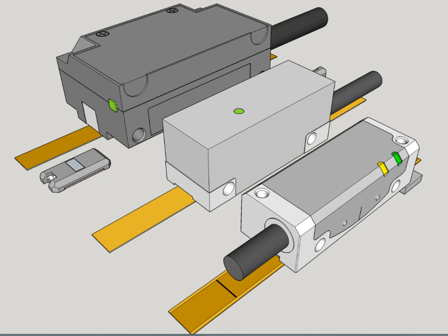The reference mark or index pulse is also output in digital form, as a pulse which is 1 to 4 units of resolution wide. The output signals may be directly transmitted to a digital incremental encoder interface for position tracking. The major advantages of linear incremental encoders are improved noise immunity, high measurement accuracy, and low-latency reporting of position changes. However, the high-frequency, fast signal edges may produce more EMC emissions.